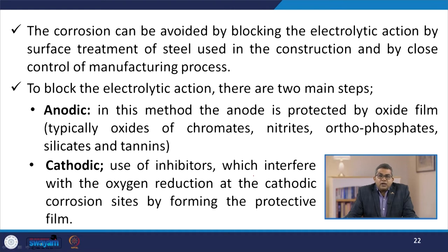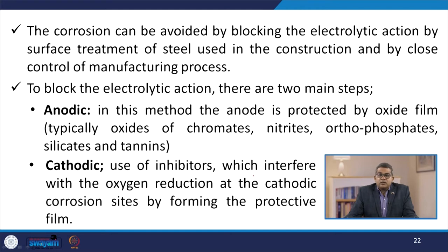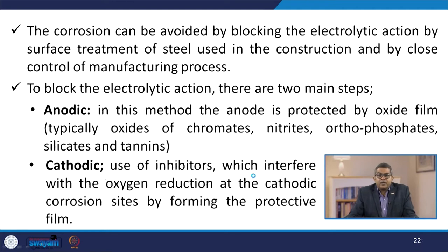To block the electrolytic action, there are two main steps. The first is anodic protection: the anode is protected by an oxide film, typically oxides of chromates, nitrites, orthophosphates, silicates, and tannins. The second is cathodic protection: use of inhibitors which interfere with the oxygen reduction at cathodic corrosion sites by formation of a protective film, so that corrosion cannot take place.